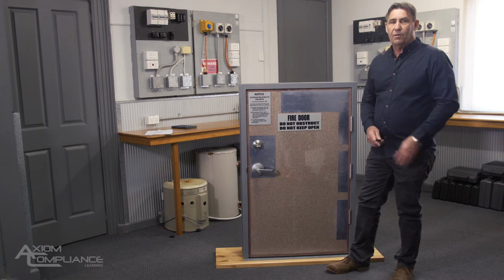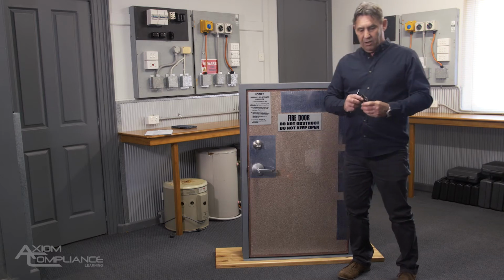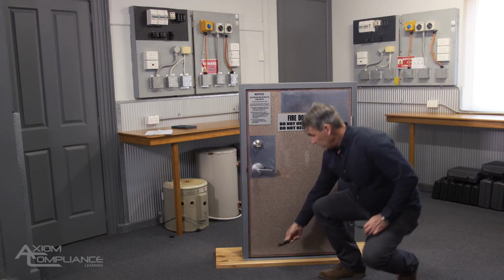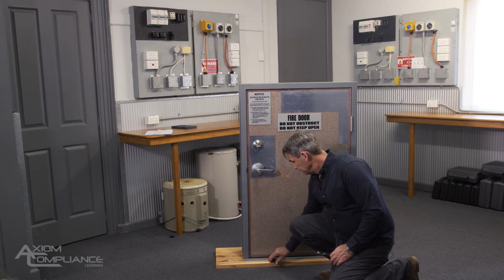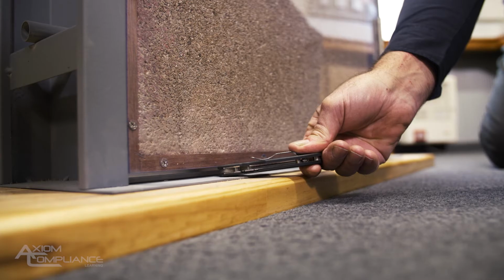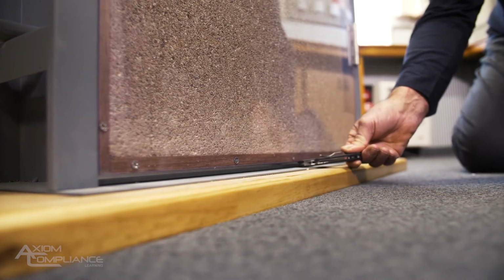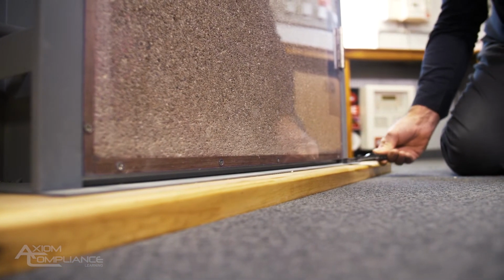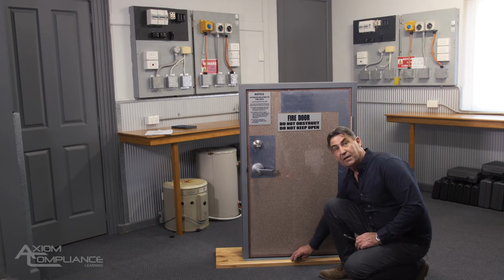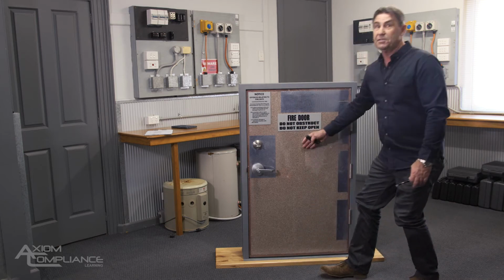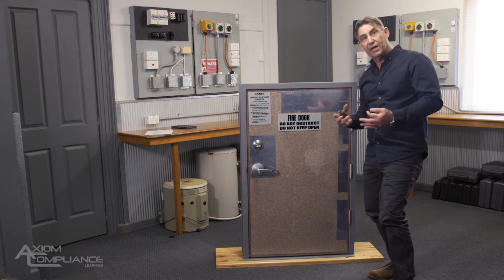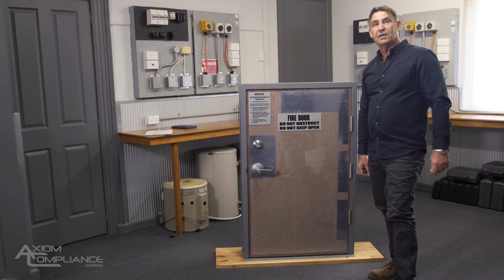On the bottom of the door, my pocket knife is almost exactly 10 millimeters. So if I can fit that pocket knife underneath the door, that is less than 10 millimeters, it's perfect. And I also want to show you on the bottom of the door, I've got another seal as well, called a drop seal. A drop seal is another mechanism that you can use if your gaps get a little bit big. It's very expensive to replace these doors, and we've got different ways that we can compensate for small changes to the door, and I'll just mention those as we go along.